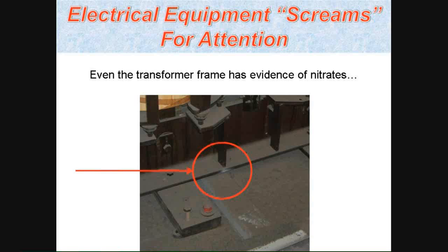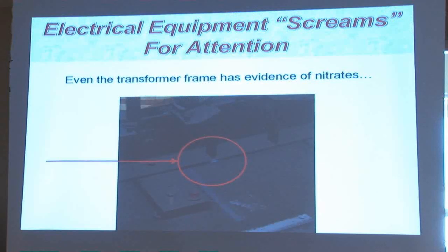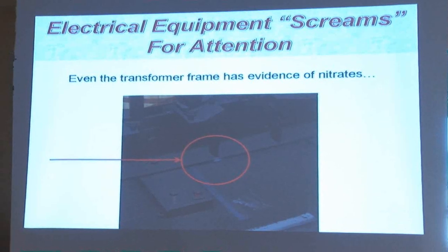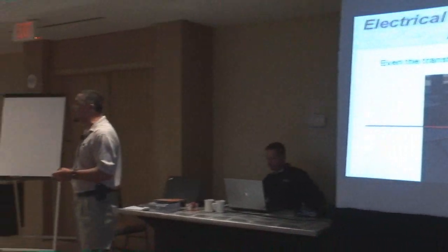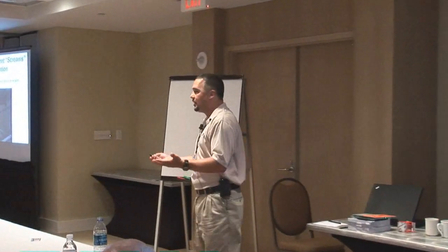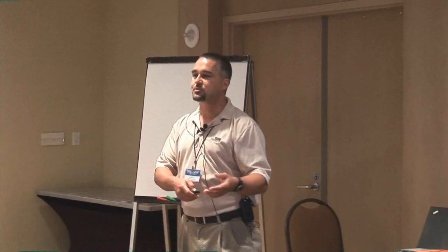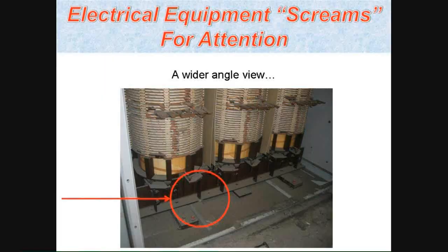So we knew that we were correct in our assumption without ever opening the equipment, and it never could have been identified without using the ultraprobe and knowing how to analyze that stuff properly, convincing the customer we do need to shut it down. And that's what they did. And as you can imagine, in a hospital, it is a logistical nightmare to coordinate shutting anything down. But we were able to accomplish that, get it open, and clean it up because the switch is so old there's not replacement parts available, but they're on order, and there's a planned shutdown coming up.